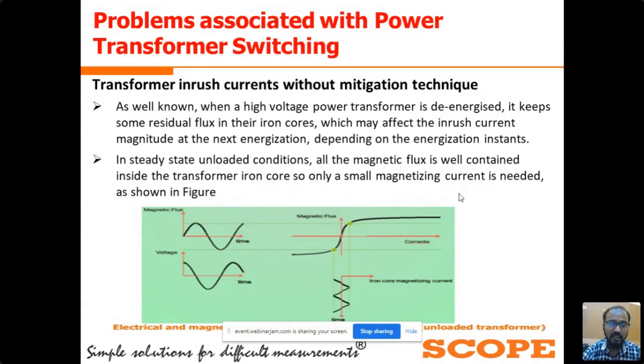If we consider our 400 kV, 765 kV system, there are large rating power transformers, near 500 MVA, 1500 MVA. So the full load current for these power transformers is very high. There is a high inrush current during the energization of the power transformer. The main reason for this high inrush current is that whenever we de-energize the power transformer, it keeps some residual flux in the iron cores of the power transformer. This residual flux affects the inrush current magnitude at the next energization of the power transformer.